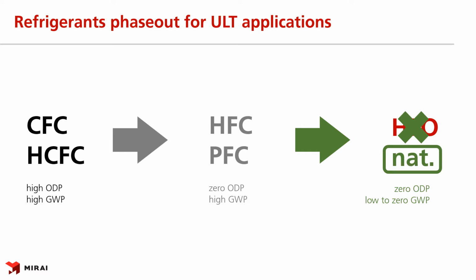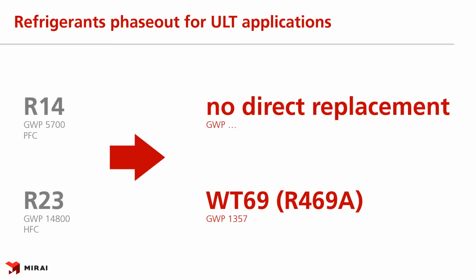That is the reason why many see the future in the natural refrigerants. A basic example of two ULT refrigerants would be R14 and R23. To my knowledge, there is no direct replacement for R14. R23 can be replaced by WT69, with the designated number R469A. You can see on the slide that WT69 reduced the global warming potential of R23 by 90%, but still has a GWP much higher than any natural refrigerant suitable for ULT applications. Side note, R469A is a mixture of R744, R32, and R125.